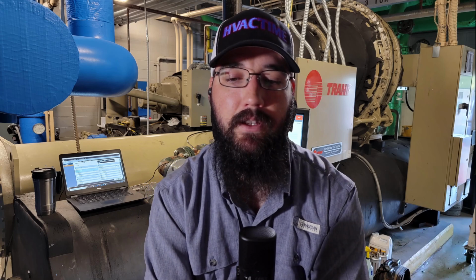What I mean by that is a lot of technicians, especially on the commercial side, typically have valves that we have to manually calibrate ourselves. We have to make those adjustments, and while they may come from the factory preset fairly close, depending on your circumstances, they may not be where they need to be for your specific application. And that's for a TXV, right? And so the issue that we've always had with TXV is technicians having a deep enough understanding or having the time to properly calibrate the valve upon install. And that was a major failure point.